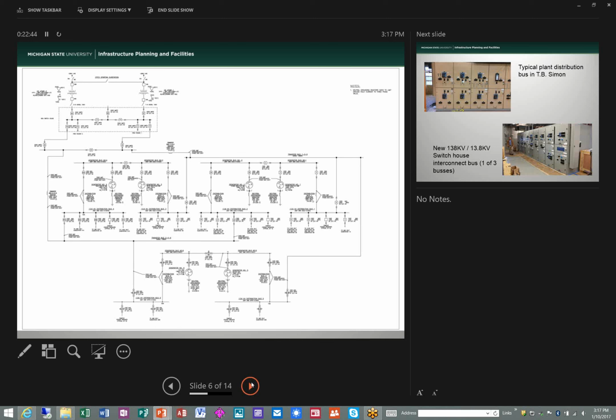We've got a lot of reactors, a reactor between each generator bus and distribution bus. We've got reactors on our transfer buses before the interconnection with our utility tie. Like Bob mentioned, up until October of this year, we were on a 46 kV to 13.8, 25 megawatt basically substation, 2 transformers in parallel. We've run that way since the plant was built. We added the second one in like 1989 or something.